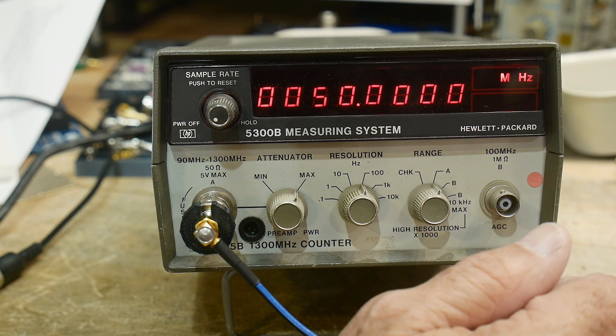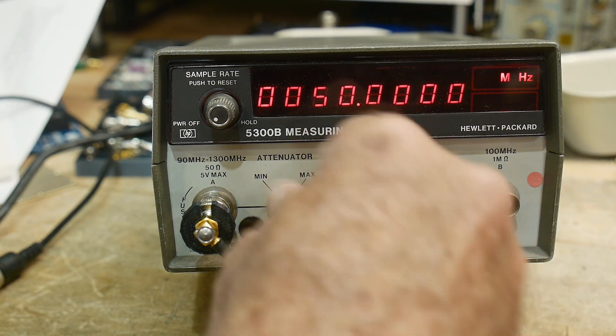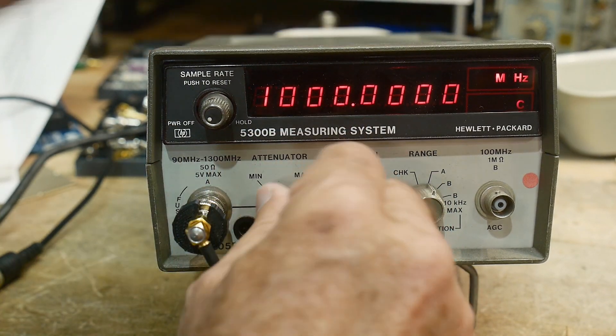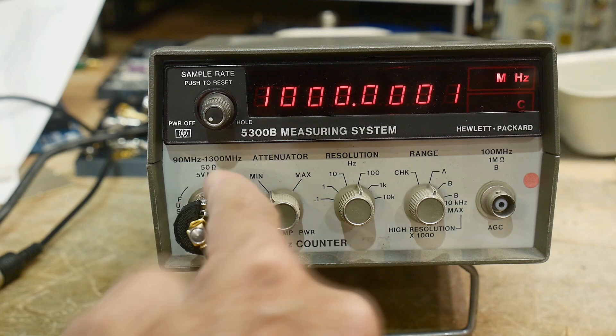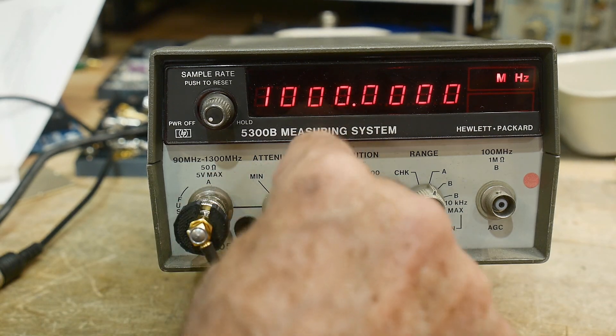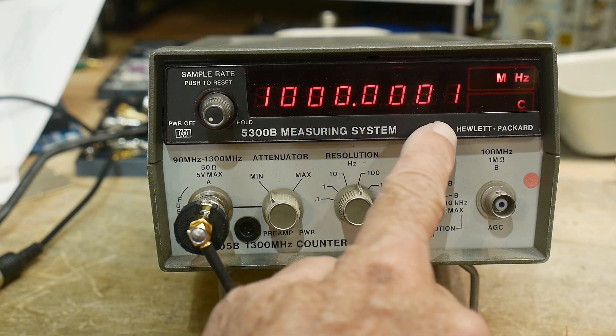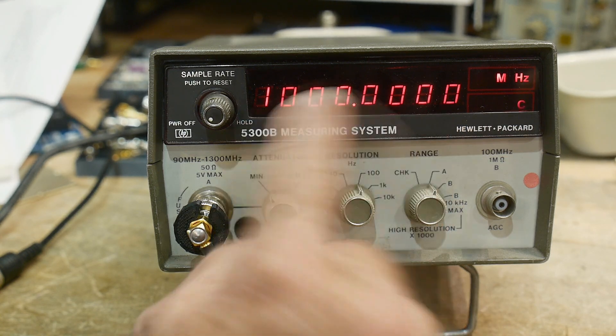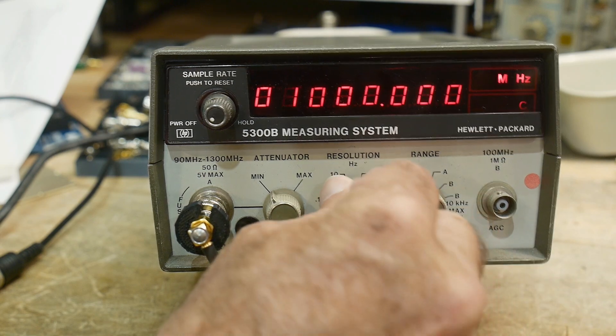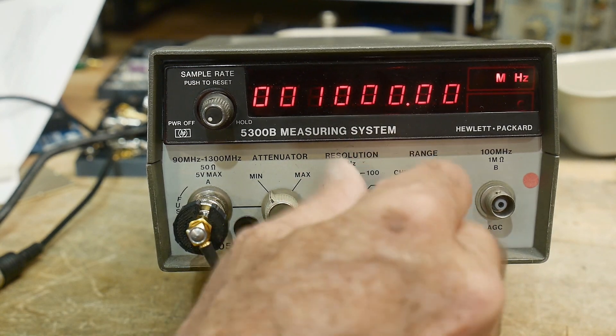I'm not seeing any signal and that's because I have the attenuator set to max. If I set the attenuator to min, there we go. This is a turn, I thought it was a click, but it's a turn. Minimum attenuation on the input, maximum attenuation on the input it couldn't see it. So here on minimum you can see that we're now counting one gigahertz or a thousand megahertz.